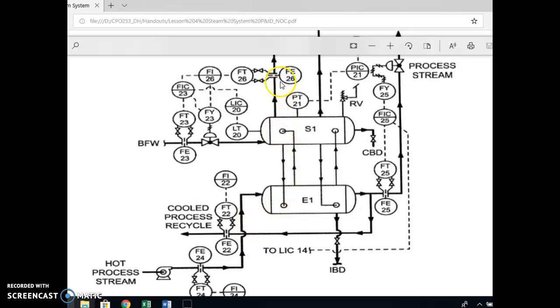If I want to increase my steam production, that means I want FE26 to be increased by 10%. This is FE26 here. I have to get my E1, the exchanger. I need hotter liquid to come through here to cause the boiler feed water to boil, to have a higher rate of boiling. To boil more of the boiler feed water at a higher rate, we're just going to be boiling at a little higher temperature. We'll have more volume. So the first thing I would do is I would increase my FE24, FT24, which is the flow, the hot process stream going through E1.